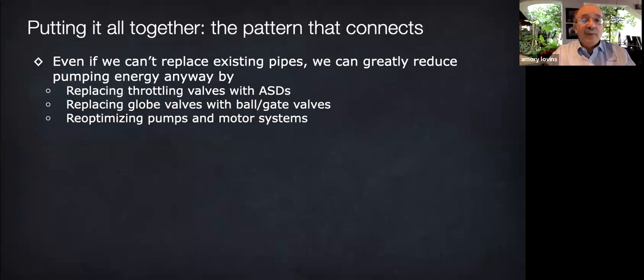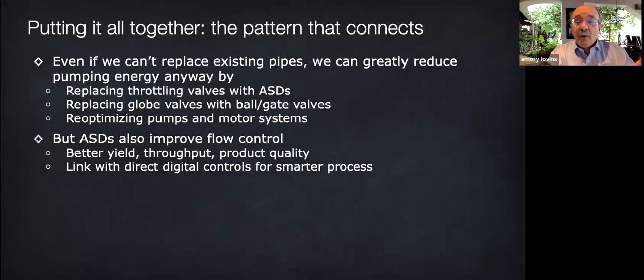Well, returning to pumping systems, it's often worth repiping, but even if you don't do that, at least the valves can be eliminated or replaced. The pumps and motors can be reoptimized. And even if flow doesn't vary much, and remember, power varies as the cube of flow, you may want real-time digital speed and flow control anyway, just to improve control of the production process.